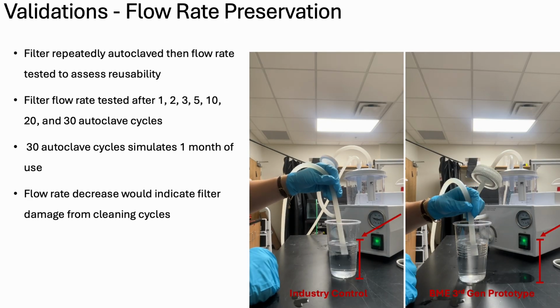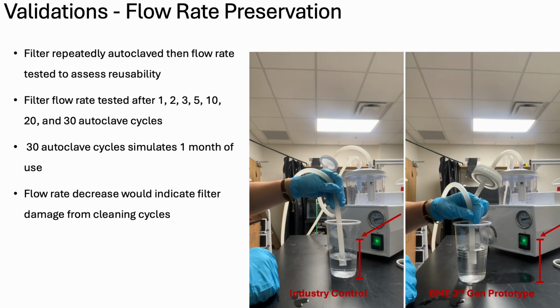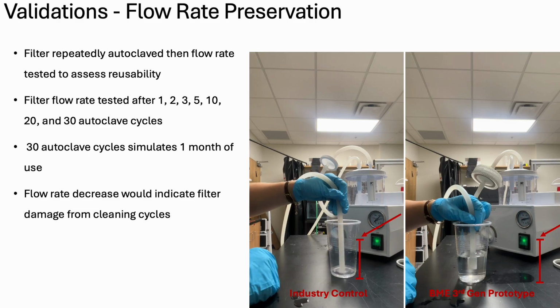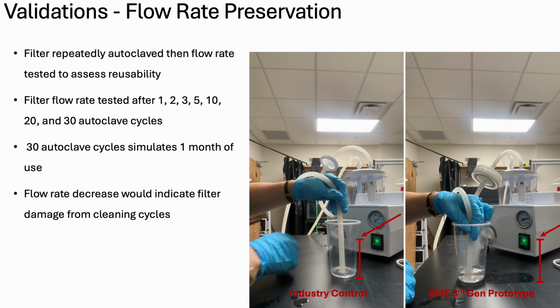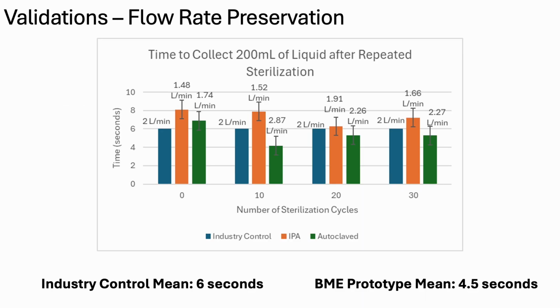For the second validation, we did a flow rate preservation test. In the video, you'll see that after just one use, the industry control filter and our prototype both maintain a similar water suction rate. Even after autoclaving our prototype, the suction performance stayed just as good, while the industry device was not autoclaved. In that same validation, we ran multiple cycles to measure how long it took to collect 200 milliliters of liquid. On average, the industry control took about 6 seconds, while our prototype actually did it in around 4.5 seconds.